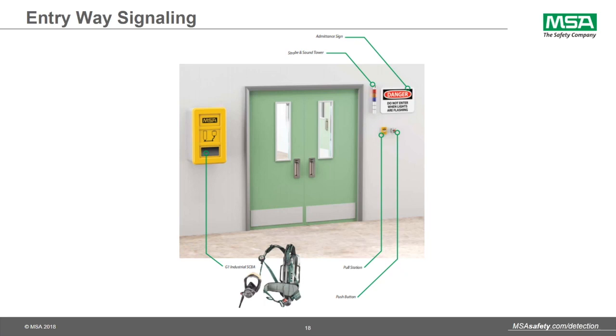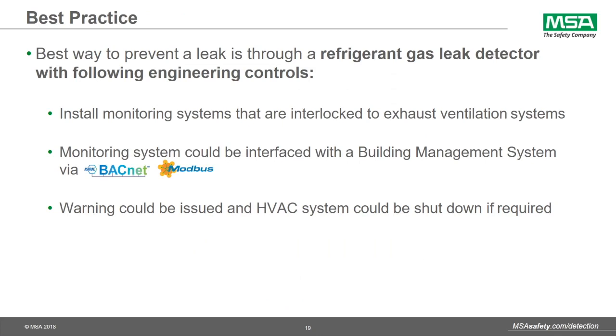As ASHRAE 15 states, each entryway signaling is required in the event of a leak to advise the safety of the environment inside the room. We offer the complete solution of signaling devices and safety equipment such as breathing air respirators, horns, strobes, acknowledge buttons, and pull stations. Really, the best way to prevent a large leak from occurring is through a sensitive leak monitor that has the following capabilities. It should be tied to exhaust ventilation systems, should have the ability to interface with a building management system through digital or analog communication, and it should have the ability to notify facility personnel of a hazardous situation.